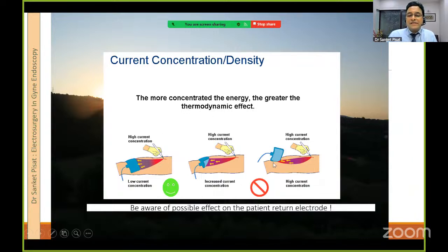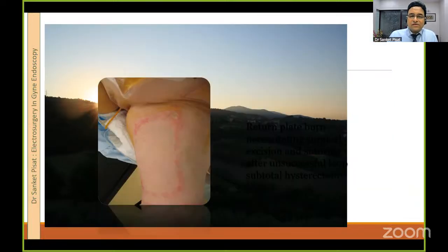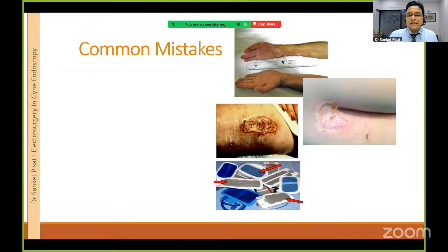The problem happens when the return electrode is not well connected. The current entry area and the current exit area almost become the same, and therefore the current does not understand that it is not supposed to coagulate at the exit, and that is where you get return electrode burns. This is what it looks like if the plate has not been connected properly and current is forced to go from all of this area rather than the center of the plate, giving rise to the return electrode burn injury. What are the common mistakes that we as doctors make when we apply the return electrode?